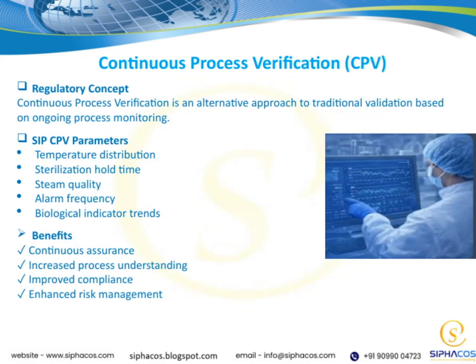Continuous process verification, or CPV, is a regulatory concept that shifts us from one-time validation to ongoing process monitoring. Instead of checking once and moving on, we keep a close eye on key parameters like temperature distribution, sterilization hold time, steam quality, alarm frequency, and biological indicator trends. This continuous approach gives us steady assurance, deeper understanding of the process, better compliance, and stronger risk management, all crucial for maintaining quality over time.